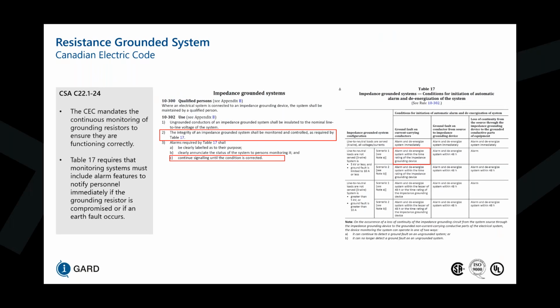In 2021, they released Table 17 on the right-hand side. And Table 17 is very useful for consultants and end users to determine the conditions in which they need to initiate an alarm or de-energize their system. So if we look at the columns here, this is the ground fault column. This is the short circuit condition. And this is the open circuit condition of the NGR. So the short circuit condition of the NGR makes the system solidly grounded. The open circuit condition makes the system ungrounded.